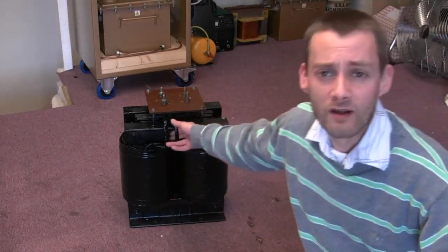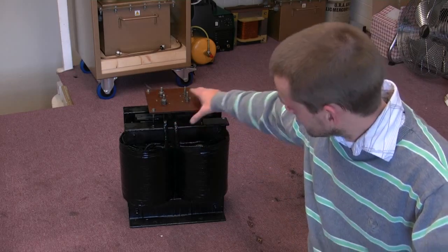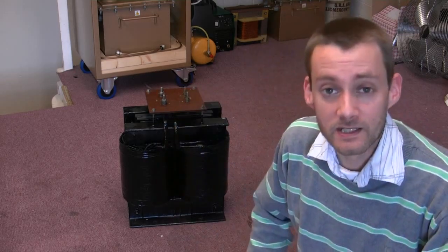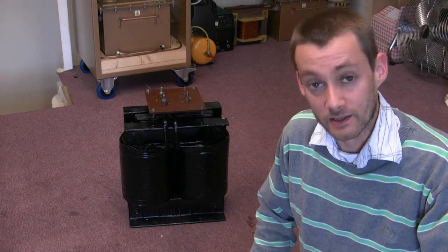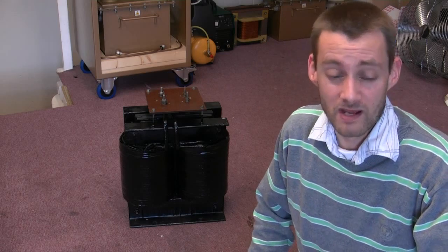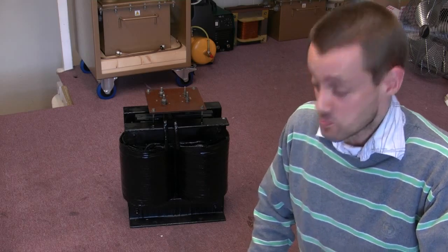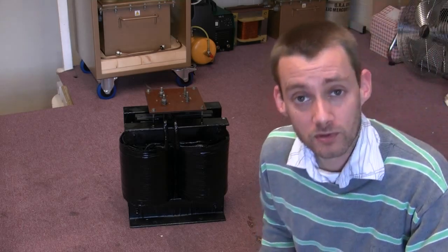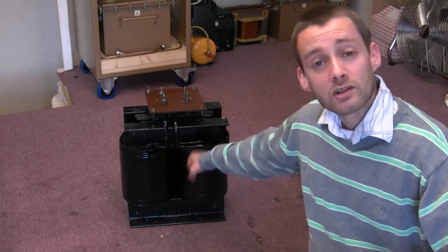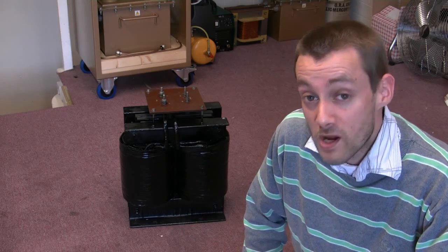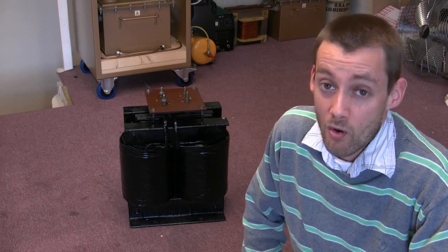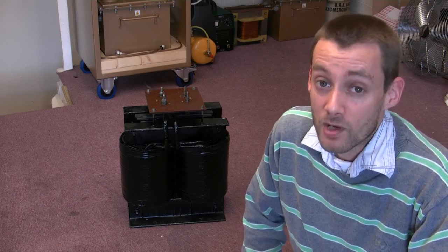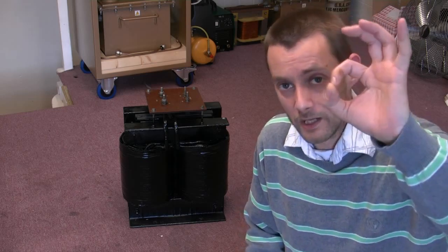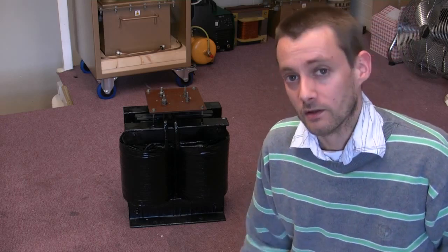Right, while I've got 5 minutes, I'm going to quickly modify this transformer. First thing I want is to take off the existing secondary windings, because at the moment I've got 60 volts, about 250 amps. I want 1000 amps. So I'm going to show you guys today how I hack that secondary off and prepare it for new windings of 275mm, that big old cable on the secondary.